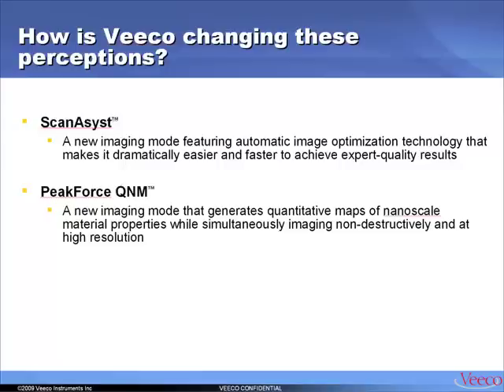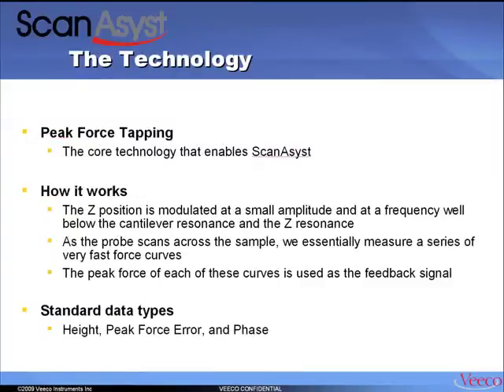The second one is Peak Force QNM. That's a new package that generates quantitative maps of nanoscale material properties while at the same time images the sample non-destructively and at very high resolution. The technology enabling ScanAsyst is something we refer to as peak force tapping. It works by modulating the Z position at a small amplitude and a frequency well below any resonance of your system. While the probe scans across the sample, we measure a series of very fast force-distance curves, with speed determined by the modulation frequency. The peak force of each of these force-distance curves is then used as the feedback signal.